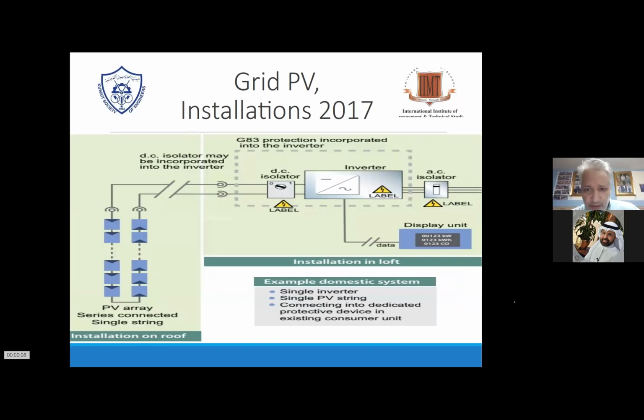So there would be an installation in the UK with the G83 protection. You can see on the left side the PV arrays serially connected. Then you mostly have the DC isolator, then the inverter, and then of course the AC isolator. It's either multi-string inverters or central grid inverters, and all of these different inverters have their pros and cons, of course.